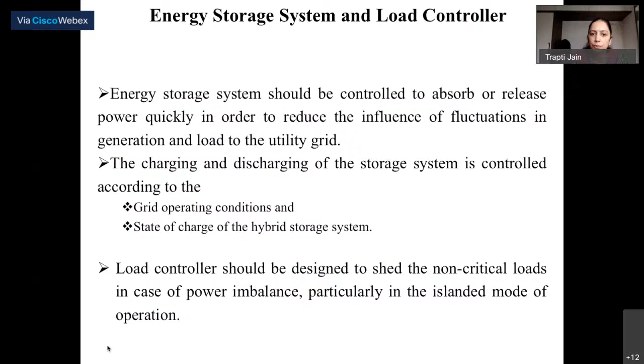Now there are control hierarchies. This hierarchical structure has three levels: primary level control, secondary level control, and tertiary level control. Primary level control is what we have seen as droop control. It controls the power sharing and the voltage and current control locally of the individual DG units. All these controls are categorized based on their response time and time scale. The primary level control is the fastest one and operates very quickly, usually in the range of 10 to 100 milliseconds. It is so fast.